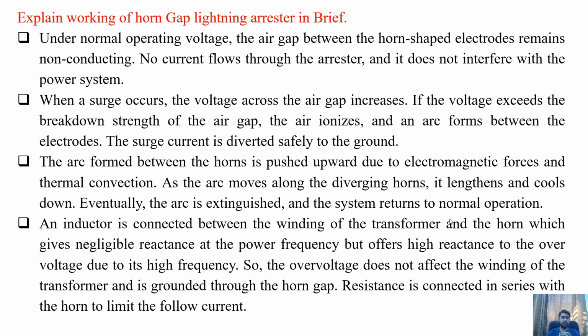When a surge occurs, the voltage across the air gap increases. If the voltage exceeds the breakdown strength of the air gap, the air ionizes and an arc forms between the electrodes. The surge current is diverted safely to the ground from the live part. The arc formed between the horns is pushed upward due to the electromagnetic force and thermal convection. As the arc moves along the diverging horns, it lengthens and cools down. Eventually, the arc is extinguished and the system returns to its normal operating condition.